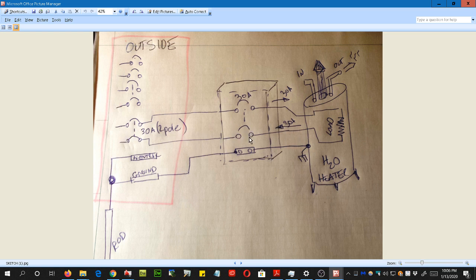Some people add these together thinking, hey, you got 30 amps going this way and 30 amps here, that's a 60 amp load. But the current only flows in a loop, so you can't get 60 here. I don't see the 60. You can't add them together unless you're in parallel.